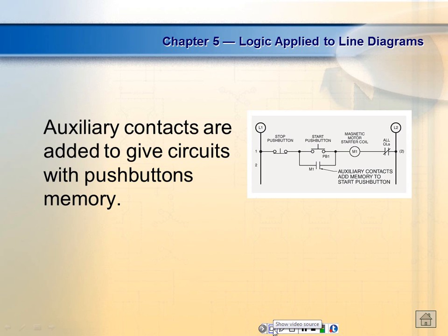So what we don't see in this diagram is somewhere there's going to be this circuit right here. And this is going to come down through, this is the symbol we use for overload sensors. Yeah, so overloads are made of two things. It's made of the sensor that senses overload, and then the contact that trips out the motor starter if an overload exists. Okay. Could heaters be hooked to the auxiliary? Could be heaters, but this is the symbol we use for overload.